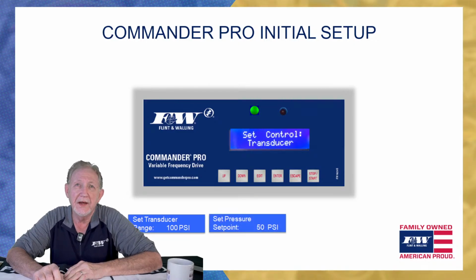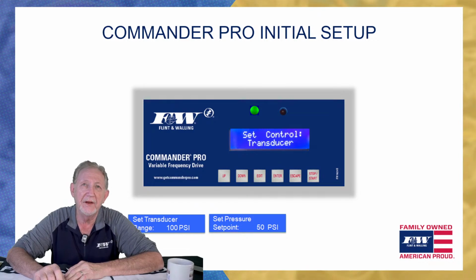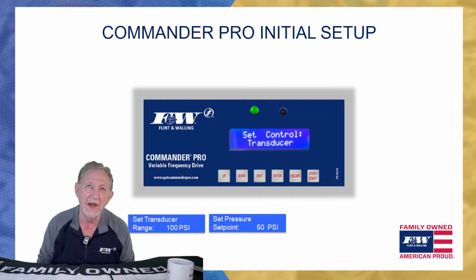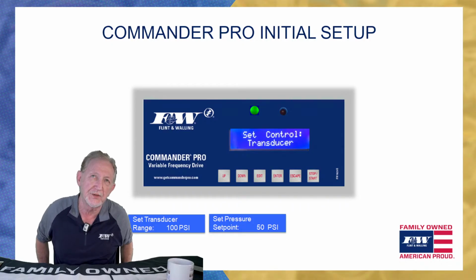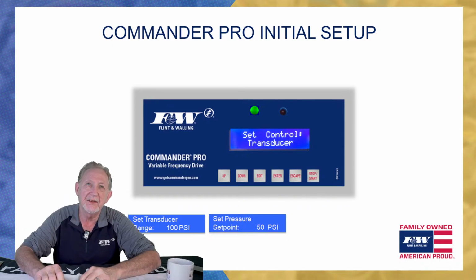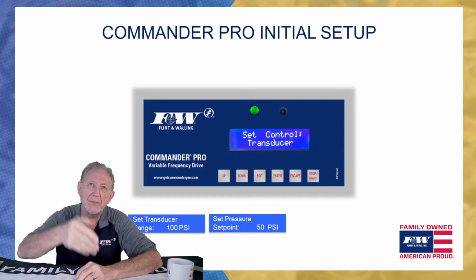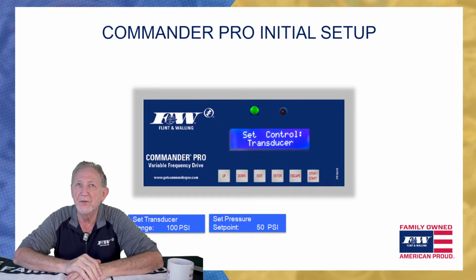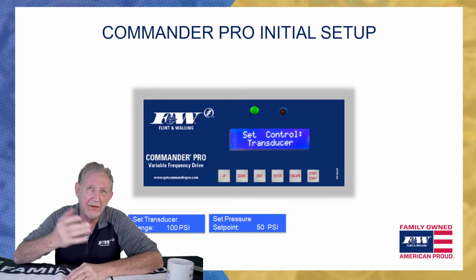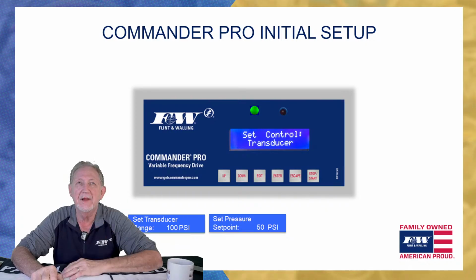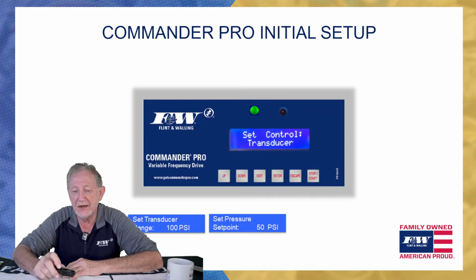It's also going to ask you to set your pressure set point here. And this is what a lot of contractors have liked over the years versus the pressure switch, is that they can actually set the pressure set point right here with their up and down scroll button. So you can run the pressure up if you want to go up higher than that 50 psi. And like I said, you can go down if you want to go lower. But that's where you're going to set that pressure set point.